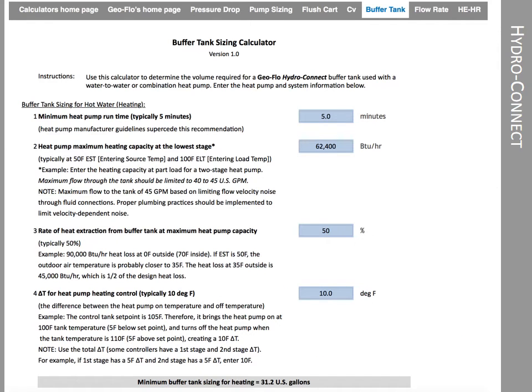Here's a screenshot from that buffer tank calculator. There are two parts. The top part is for heating, the bottom part is for chilled water or cooling. The calculator then picks the larger of the two and will determine the buffer tank size. And you can see at the bottom of the slide, in this example, it's asking for 31 gallons. And so that would be the minimum requirement for this particular application.